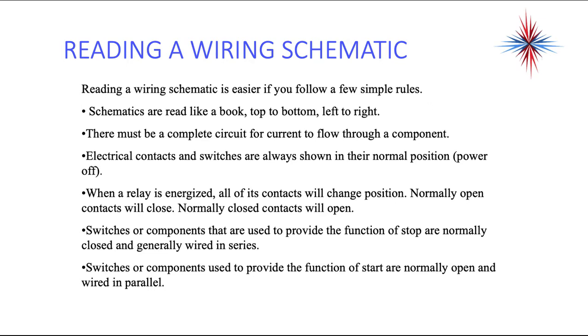When you're reading a wiring schematic, follow a few simple rules. Schematics are read like a book, top to bottom, left to right. There must be a complete circuit for current to flow through a component. Electrical contacts and switches are always shown in their normal position. That's in their power-off position.